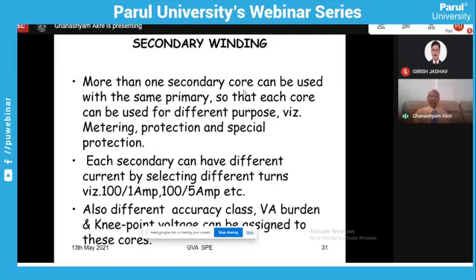More than one secondary core can be used, that I have already shown you. Each secondary can have a different current by selecting different turns, that is 100 by 1 or 100 by 5 ampere. Even the secondary amperes can be different in the different cores. So one current transformer can have one single primary but five to six secondary cores, which will be feeding different classes of equipment.